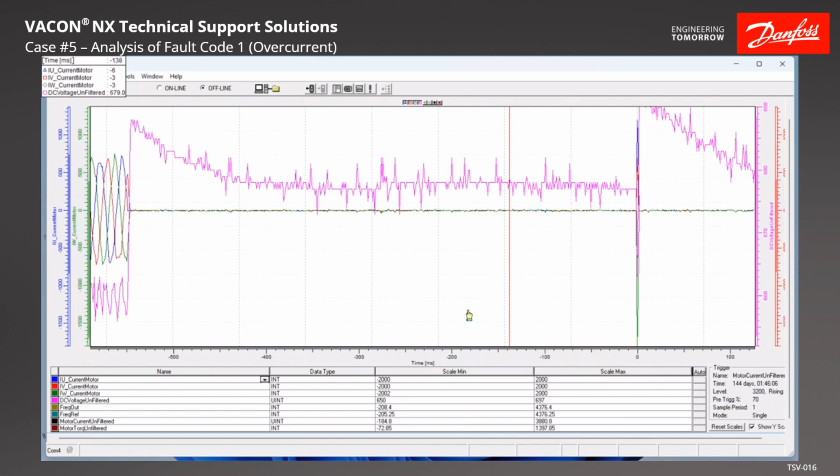Now, being a half a second, I would say it's probably not a disconnect, because I don't know that anybody could turn a disconnect off and turn it back on in that short period of time. It would probably be well over a second to do that. I'm not going to say it's impossible, but I'm just saying it's probably not likely. But you do have to eliminate it as a possibility.